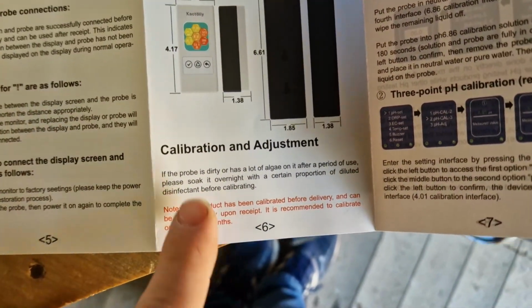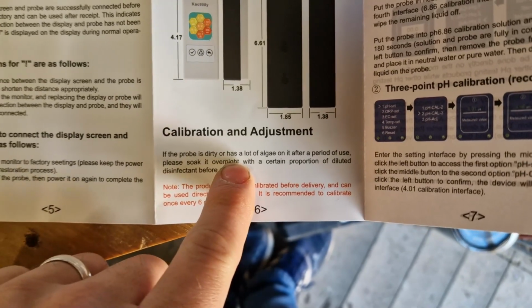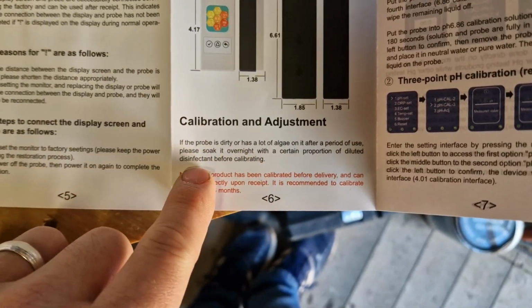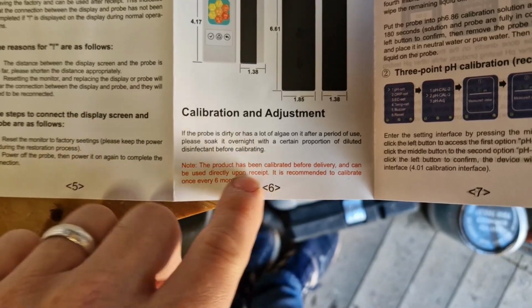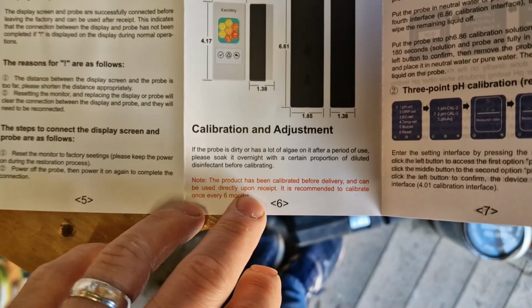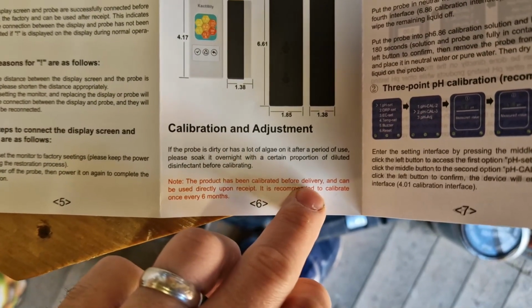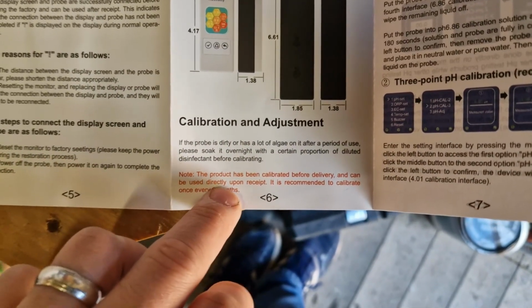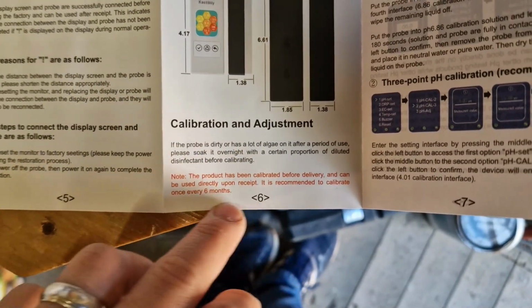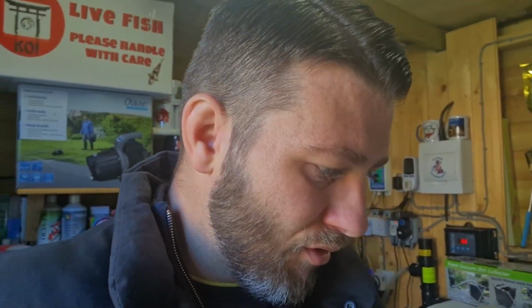Calibration and adjustment. If it's been dirty, you soak it overnight in a certain proportion of diluted disinfectant before calibrating. The product has been calibrated before delivery and can be used directly upon receipt. It is recommended to calibrate once every 6 months. So yeah, they're saying that this should be able to go 6 months before it needs recalibrating. Possibly a bit of a long stretch, especially with pH and things like that, but we shall see.